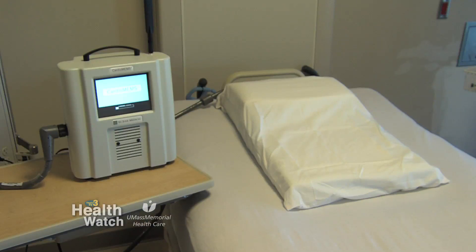The device is very simple, has a couple of components, and does not include a battery, but has instead a partner in this pillow. It's simple to take readings — all the patient has to do is lie down on the pillow and press the remote button. It takes 18 seconds to get a reading, which gets transmitted to a website. Our staff in the heart failure program then monitors the readings on a regular basis.